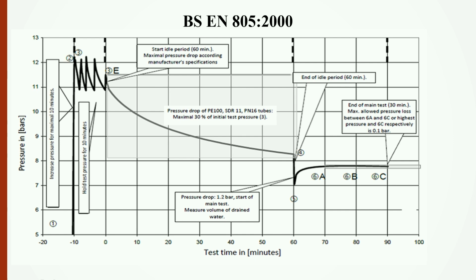You then stop the pumping and isolate the loop itself. The pressure will then drop naturally over a 60-minute period. If it drops by more than 30%, the test has failed; the pipe has got a hole in it. Then you have a rapid reduction phase, which is 10% of the original test pressure. I'm saying 1.2 bar, you'll be saying 17.6 psi. You then monitor the pressure for 30 minutes as the pipe rebounds, taking a pressure reading every 10 minutes. If the pressure between those two phases doesn't drop by more than 0.1 of a bar, or 1.5 psi, then that pipework is sound. That pressure test has been used in Europe for the last 24 years, and it takes place in less than 2 hours.